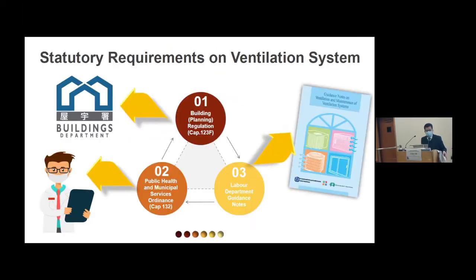In this next section, I will briefly go through the relevant statutory requirements and guidelines on ventilation. In Hong Kong, there are three main regulations stipulating the statutory requirements on ventilation systems in buildings. The Building Planning Regulations specify the requirements on providing adequate ventilation for buildings intended to be used as an office or for habitation. The Public Health and Municipal Services Ordinance specifies 6 classes of premises and their minimum fresh air requirement per person occupying the premises. And the Labour Department also issued a guidance note on ventilation and maintenance of ventilation systems, which specifies the fresh air supply rate for general work activities in air-conditioned areas.